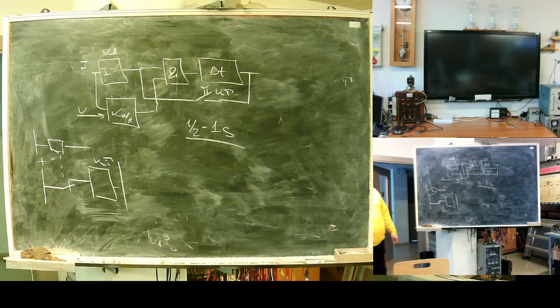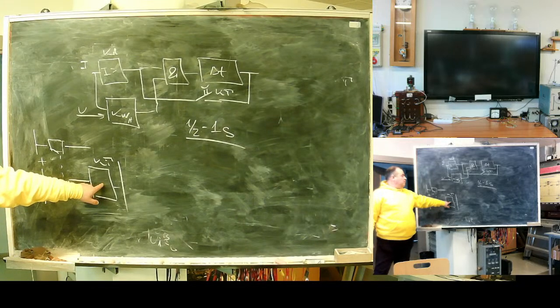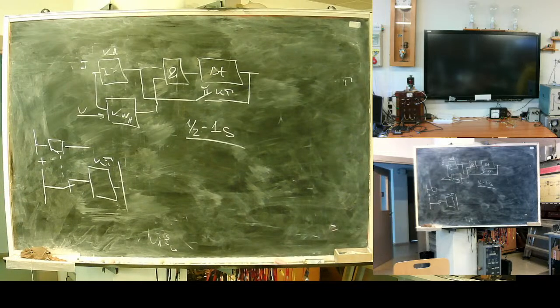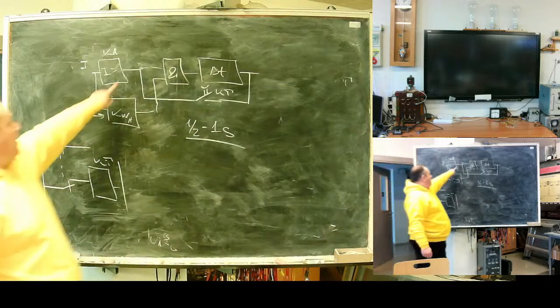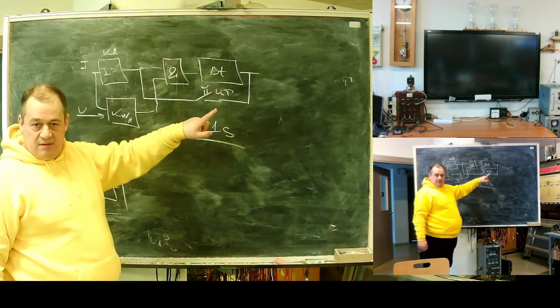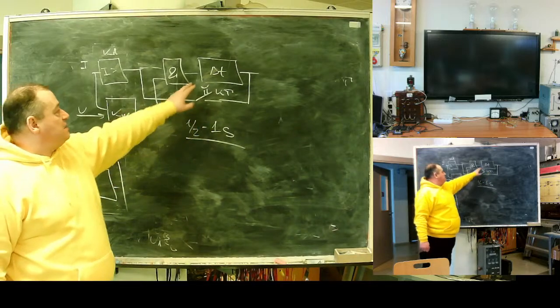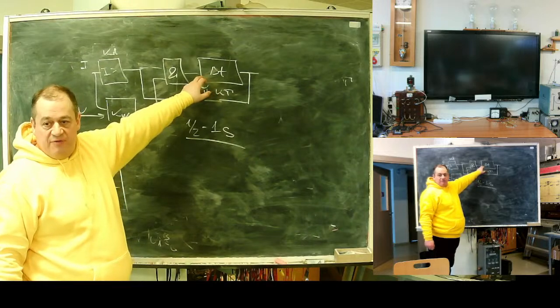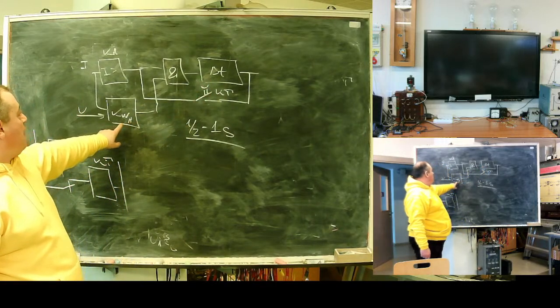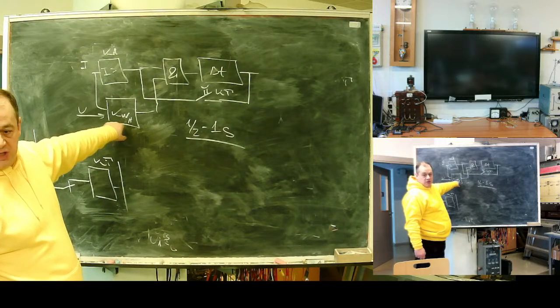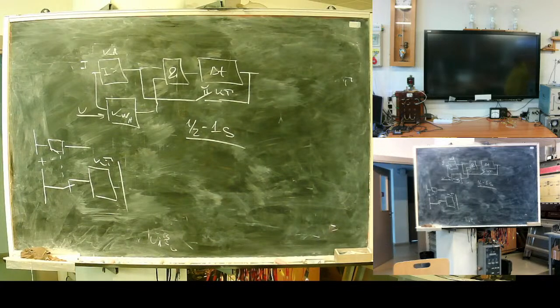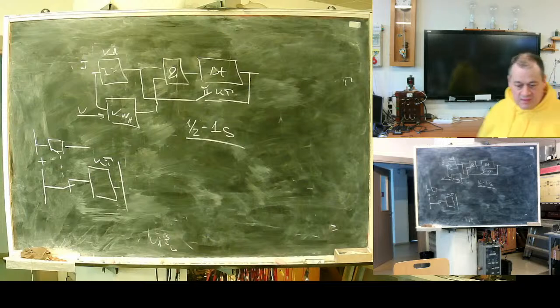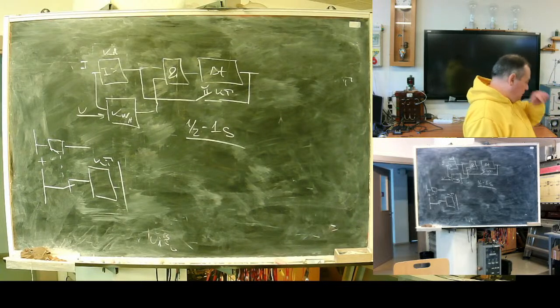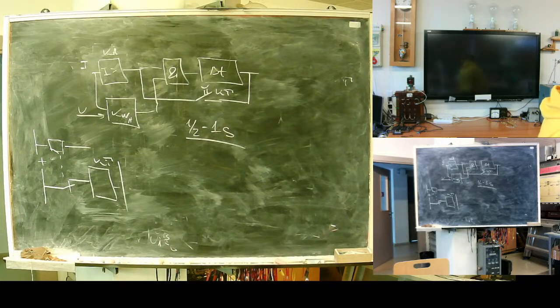How does it work? When the switch is off, this relay is energized. When you send an on command, the switch goes on. But this path is available for 1 second. What it does is set 0 time delay for the second zone, and it bypasses direction logic. So in case of switch on fault, the second zone will trip instantly. Why speed up? It makes the sensitive second zone trip instantly.